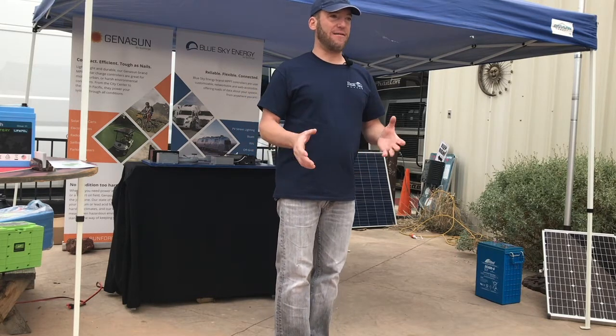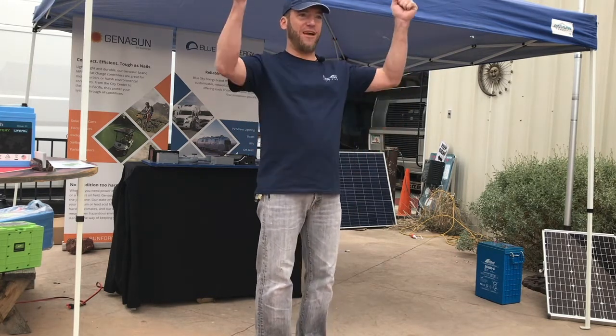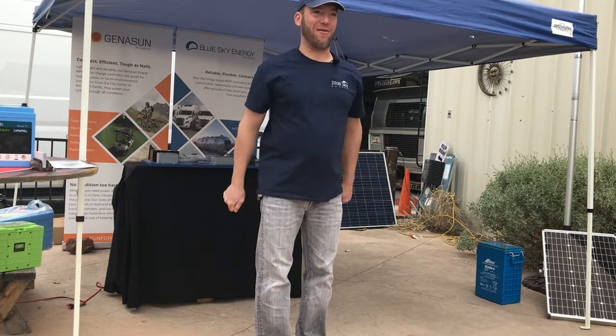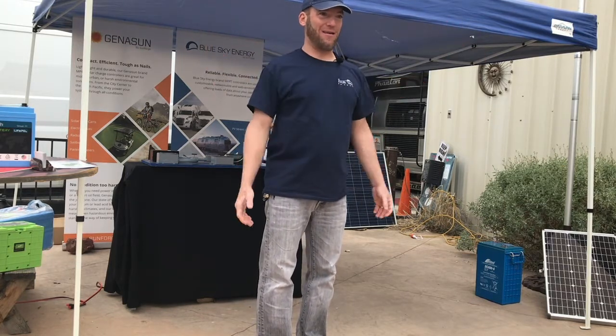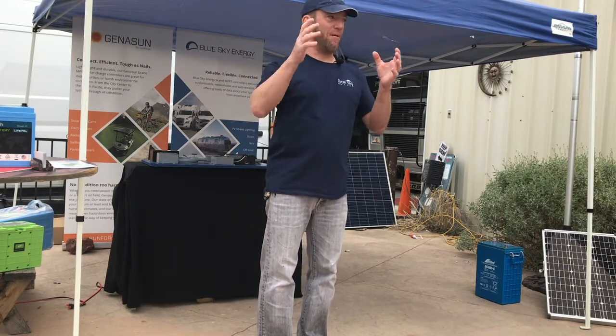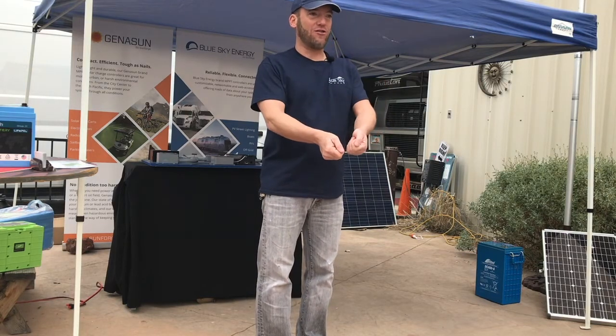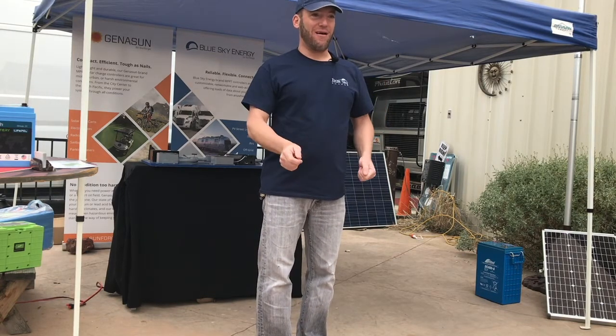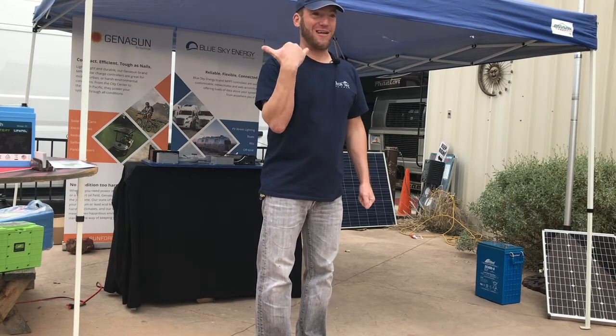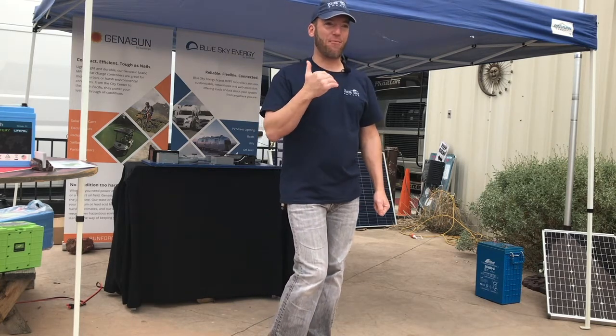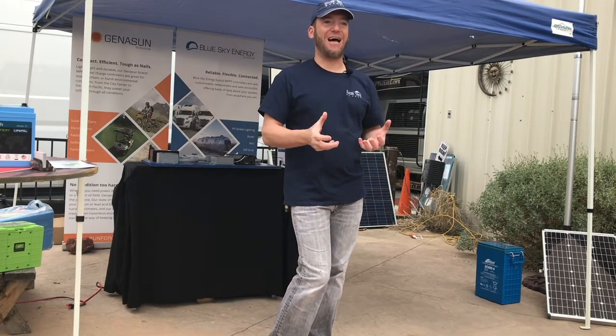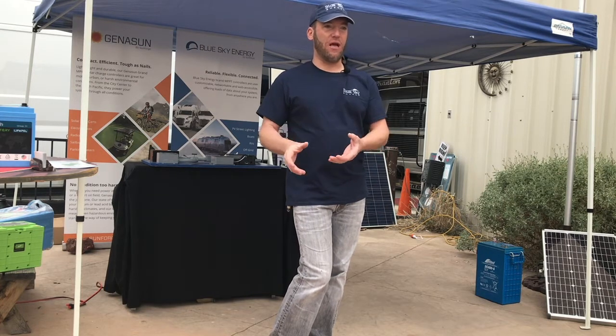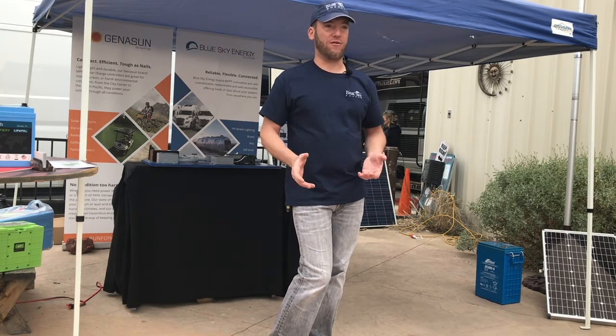It's not well known, but you can take a solar panel, face it at the sun, tie its output wires together, and leave it for a year—the panel doesn't care, it doesn't hurt the panel. But if you have a PV input connected to your charge controller and you short those wires, even with a fuse, your charge controller is dying. The fuse doesn't react fast enough to protect the charge controller if you short the PV input while the controller is energized.